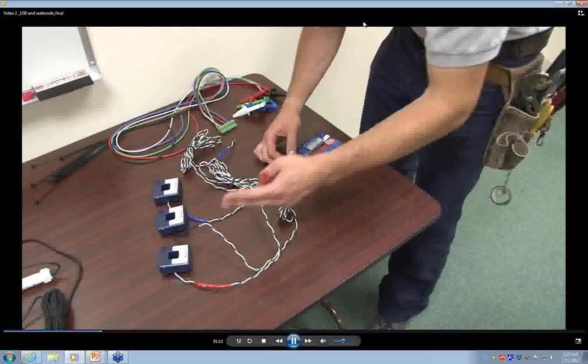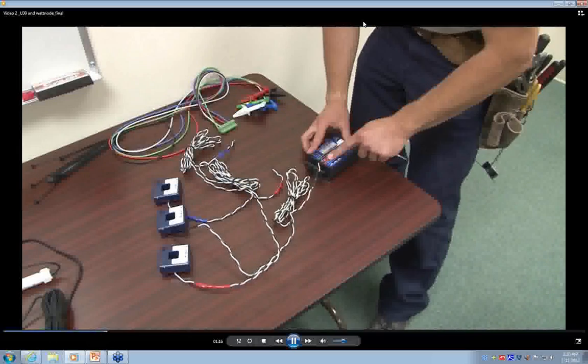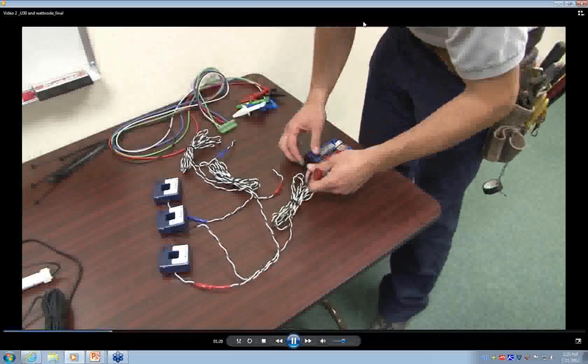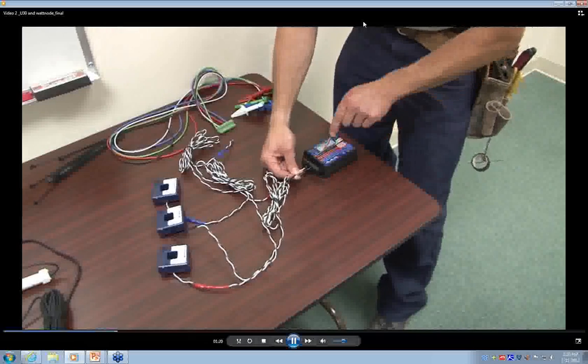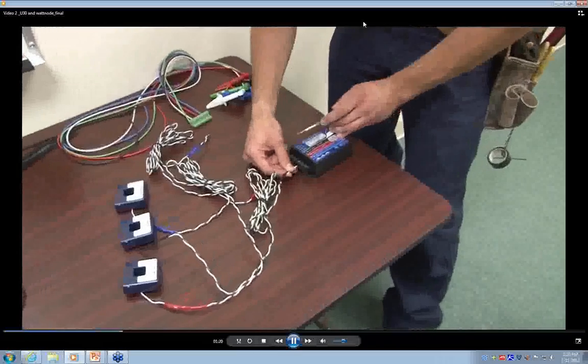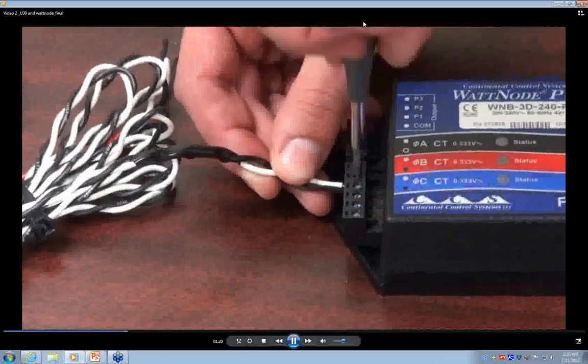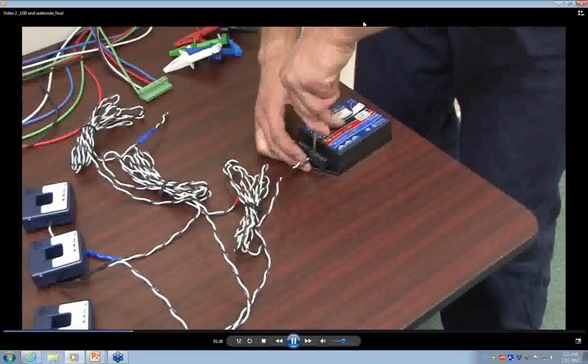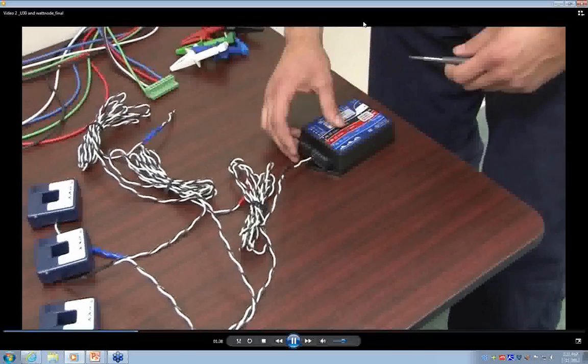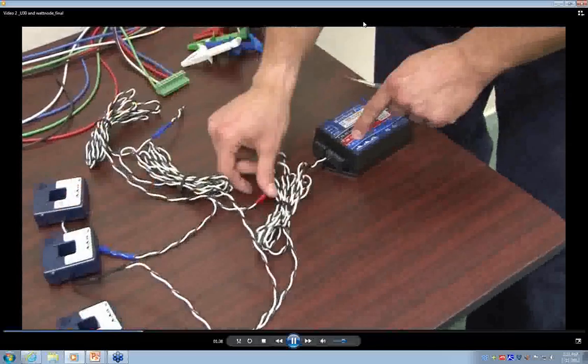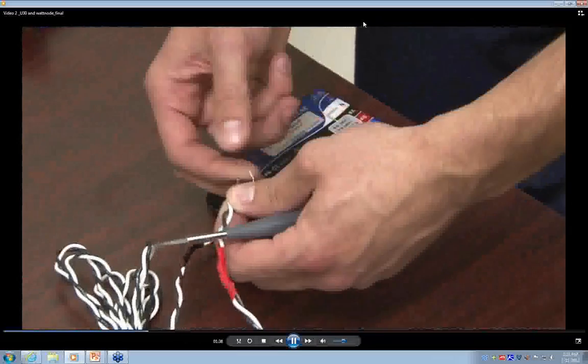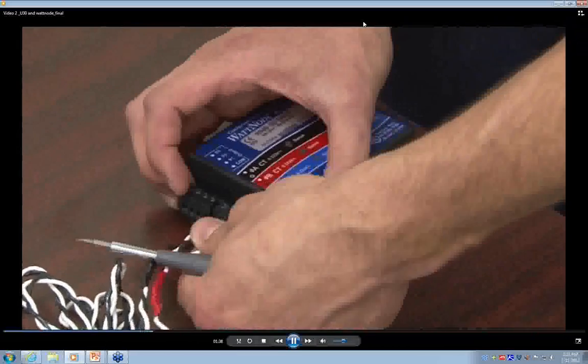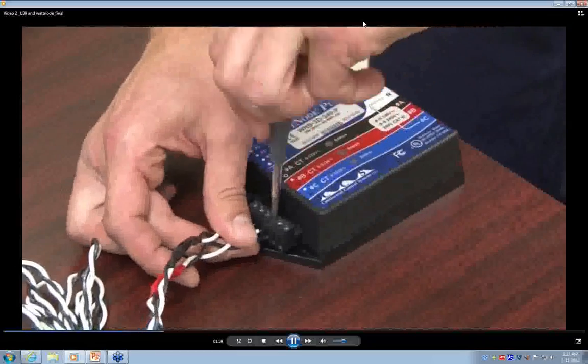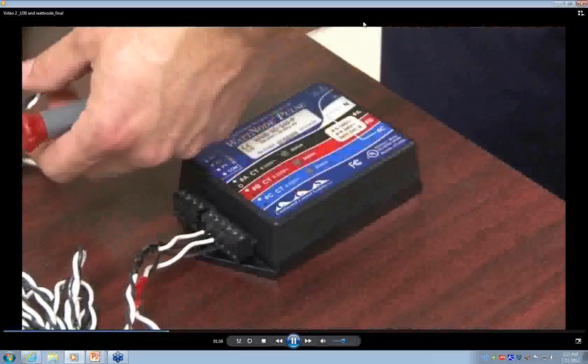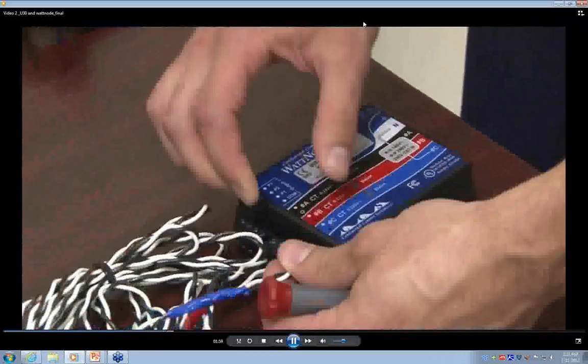I've also labeled the CTs black, red, and blue to represent the phase colors. These line up with the colors on the watt node as well as the colors in the electrical panel. We start out by wiring the black CT to the phase A terminal, to the white and black terminals. We'll then wire the red CT to our phase B terminal. Once again, the white wire will go on the white terminal and the black wire will go on the black terminal. And lastly, our phase C CT, the blue, will get wired to the phase C terminals of the watt node.